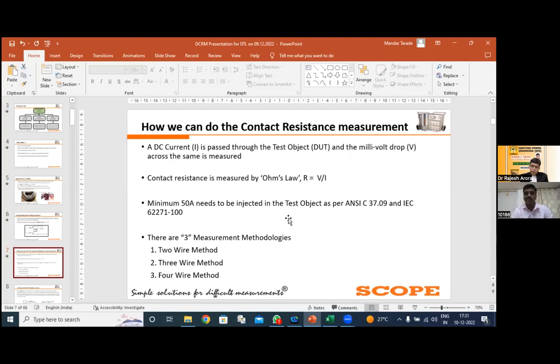as per the IEC standard 62271-100 or ANSI standard C37.09. If your value is only 40 micro ohm and you are injecting a known current of 50 ampere, you get a drop of only 2 millivolt. If you increase the current to 100 ampere, you get a drop of 4 millivolt. You have to bring that drop from the top position at 14 meter height down to the ground, where we place our equipment and do all the signal conditioning. Here, the cable plays a significant role.